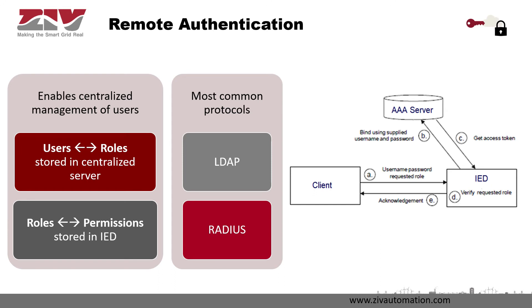The IED implements the most common protocols for remote authentication, which are LDAP and RADIUS. The IED can also be configured so that if access to the centralized server is not available, it falls back to local authentication based on the local users defined previously.